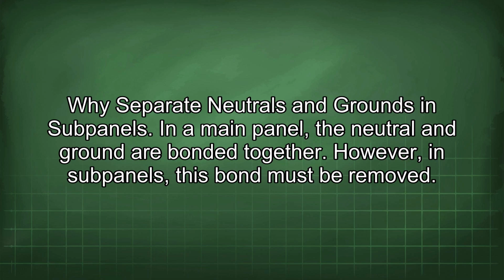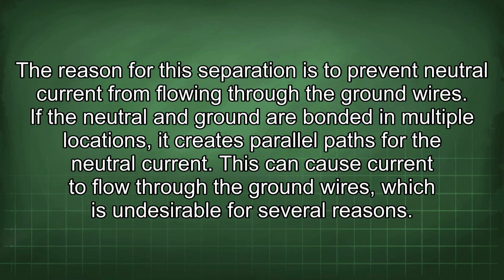In a main panel, the neutral and ground are bonded together. However, in subpanels, this bond must be removed. The reason for this separation is to prevent neutral current from flowing through the ground wires. If the neutral and ground are bonded in multiple locations, it creates parallel paths for the neutral current. This can cause current to flow through the ground wires, which is undesirable for several reasons.